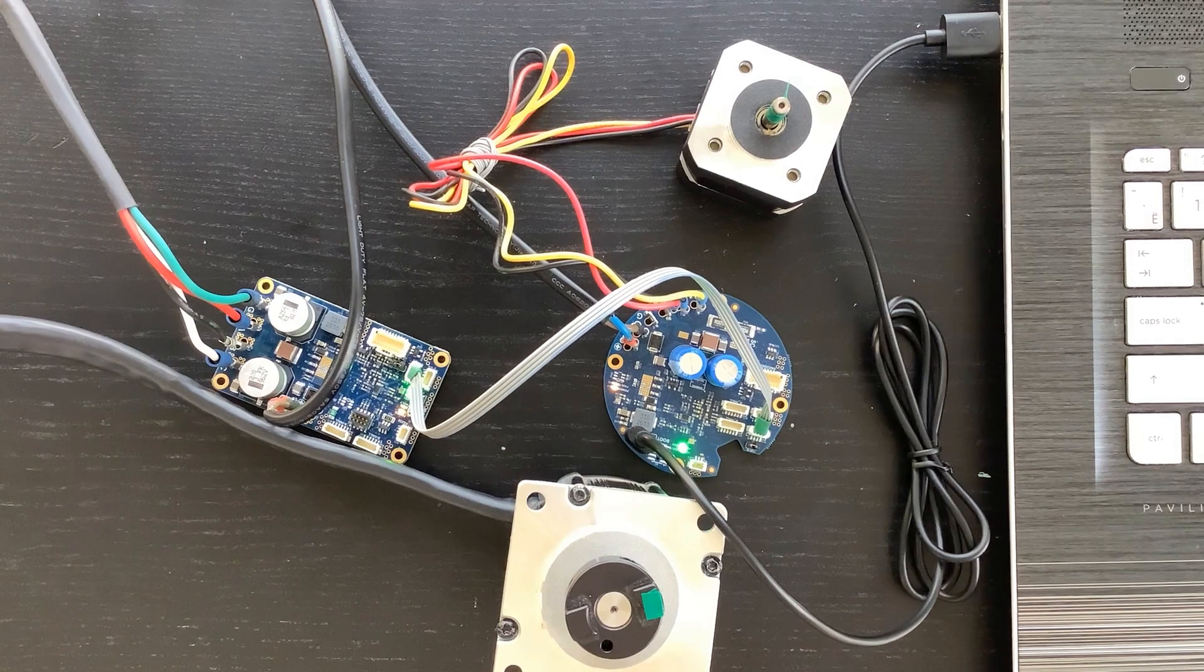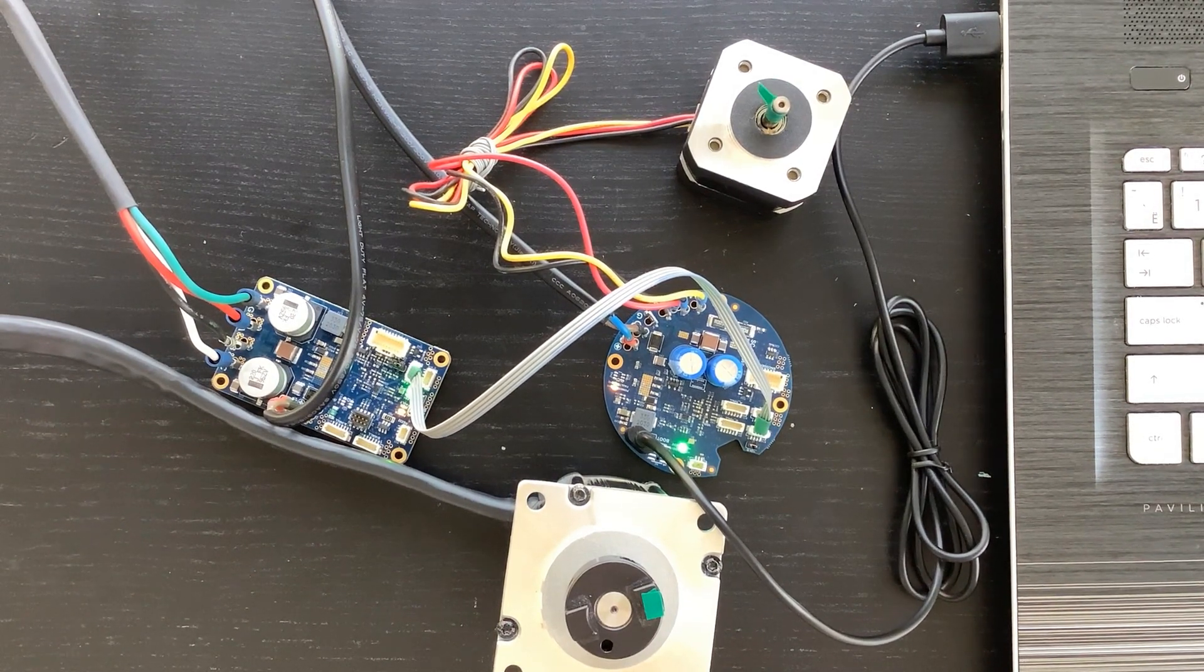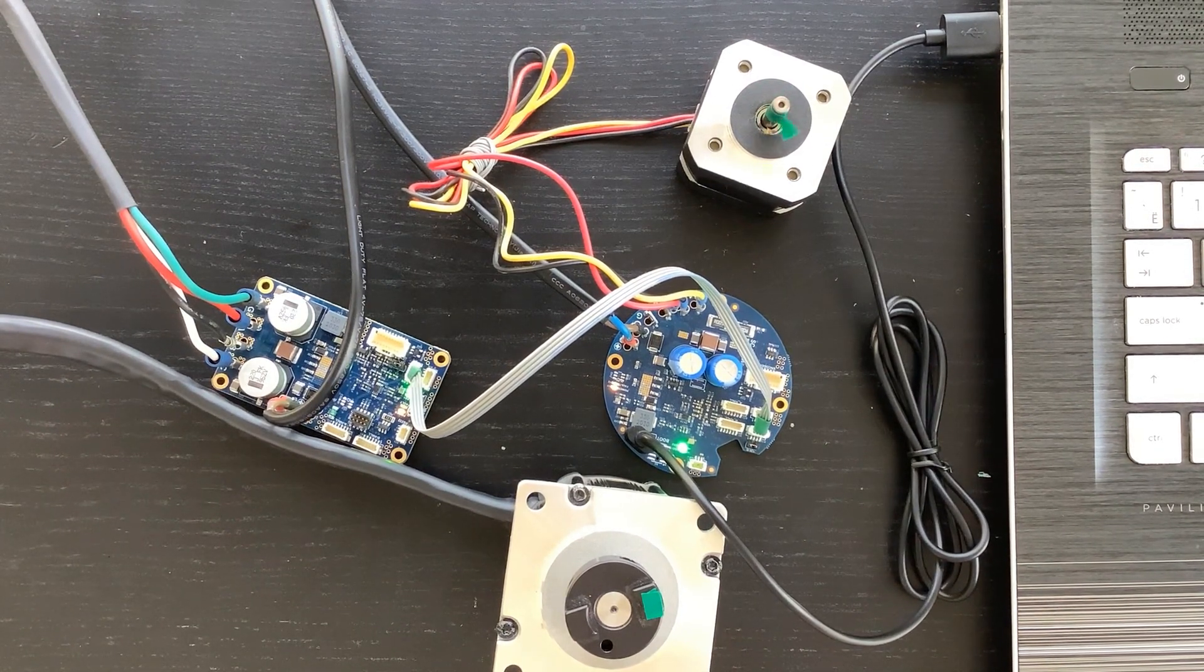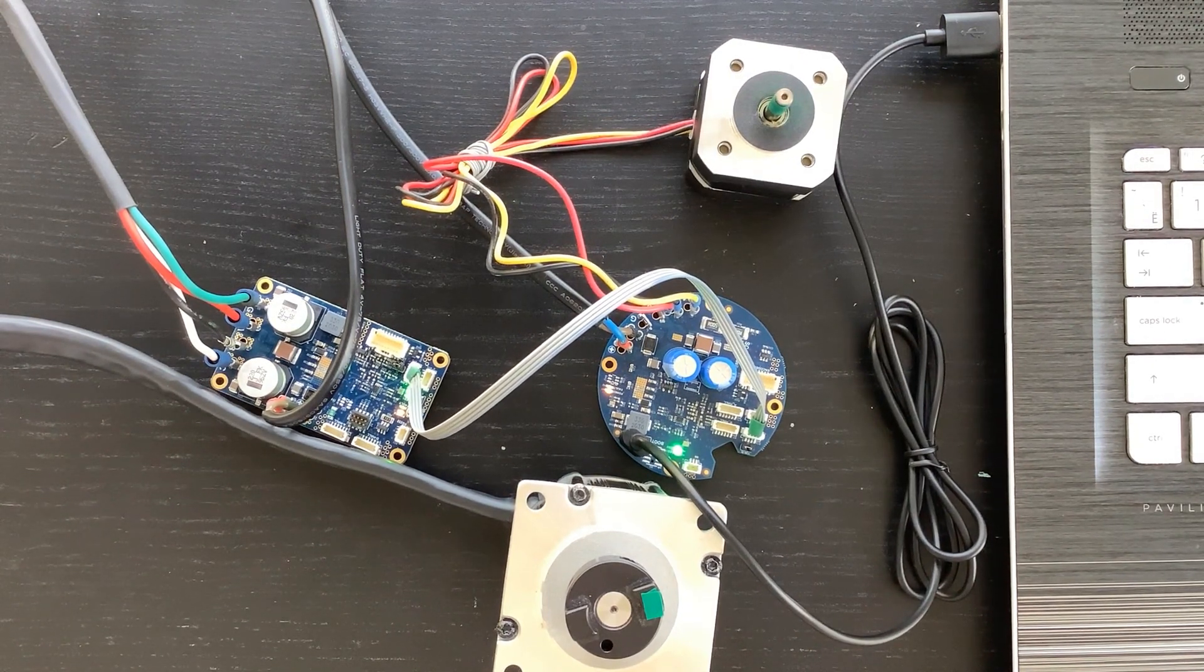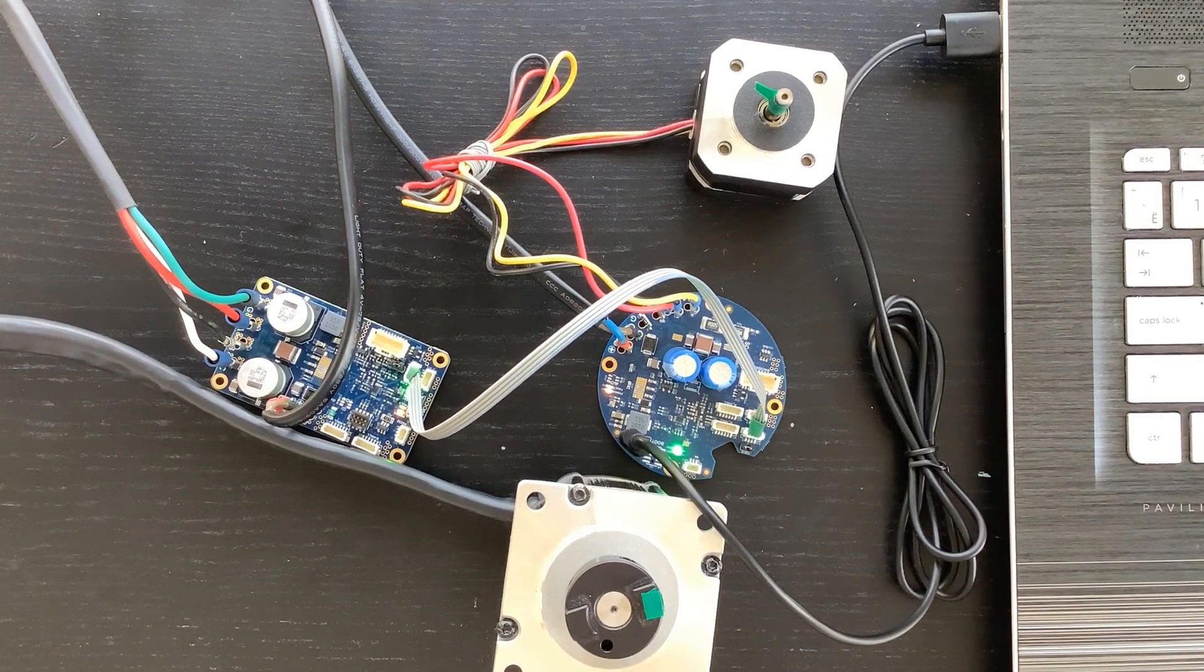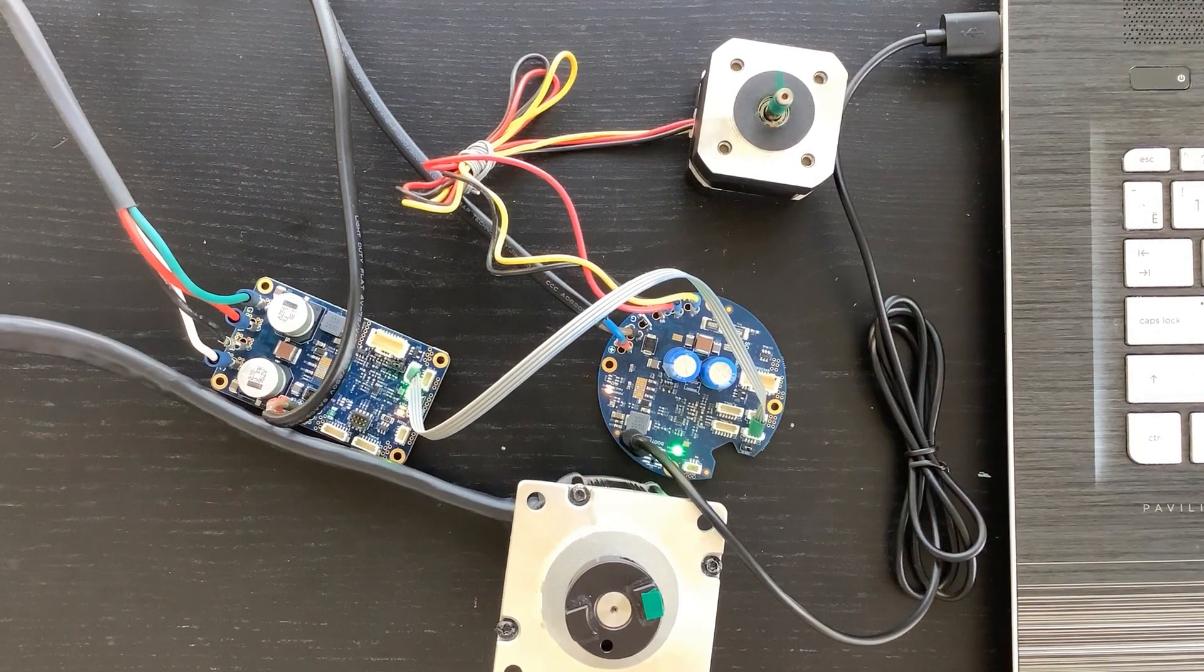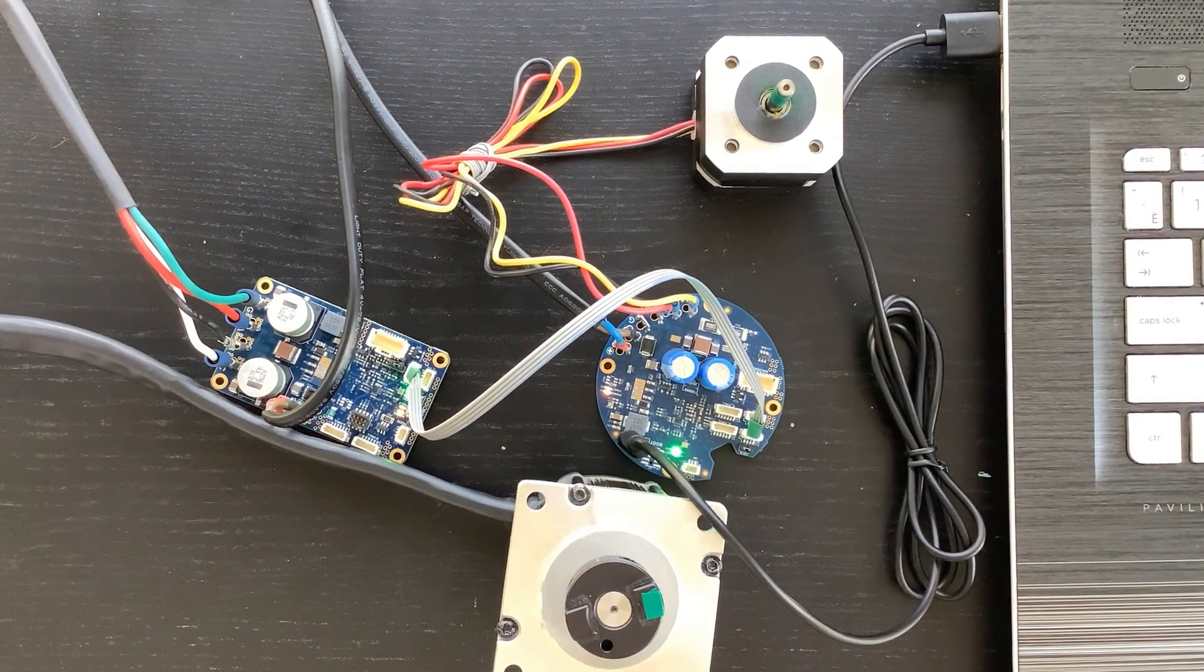Look at the smaller motor. It is making what looks like mysterious kung fu moves. What actually is happening is that its controller is automatically measuring various characteristics of the motor. The measurement routines cause the motor to make the moves. The motor accelerates to its maximum speed. Be careful as the motor is producing its maximum torque at this moment. The rapid accelerations may take place a few times during the auto configuration procedure.